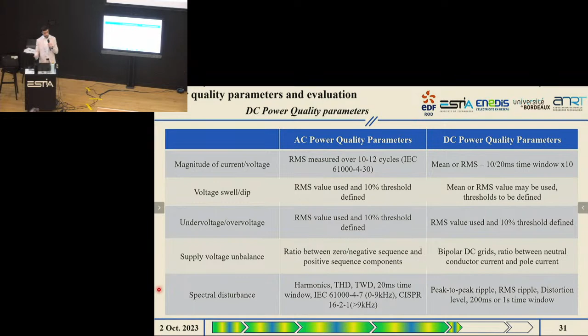And there are several indicators and parameters that could be used. One that is quite important for our research is the spectral disturbance one, because we are trying to assess and address the subject of steady state phenomena in power quality. And in AC, this indicator is particularly evaluated through a set of parameters such as harmonics, or THD, or TWD. And in DC, a parallel analysis could be done in which we could use the concept of ripple, which consists of all the components in a DC voltage or current apart from the 0 Hertz component.